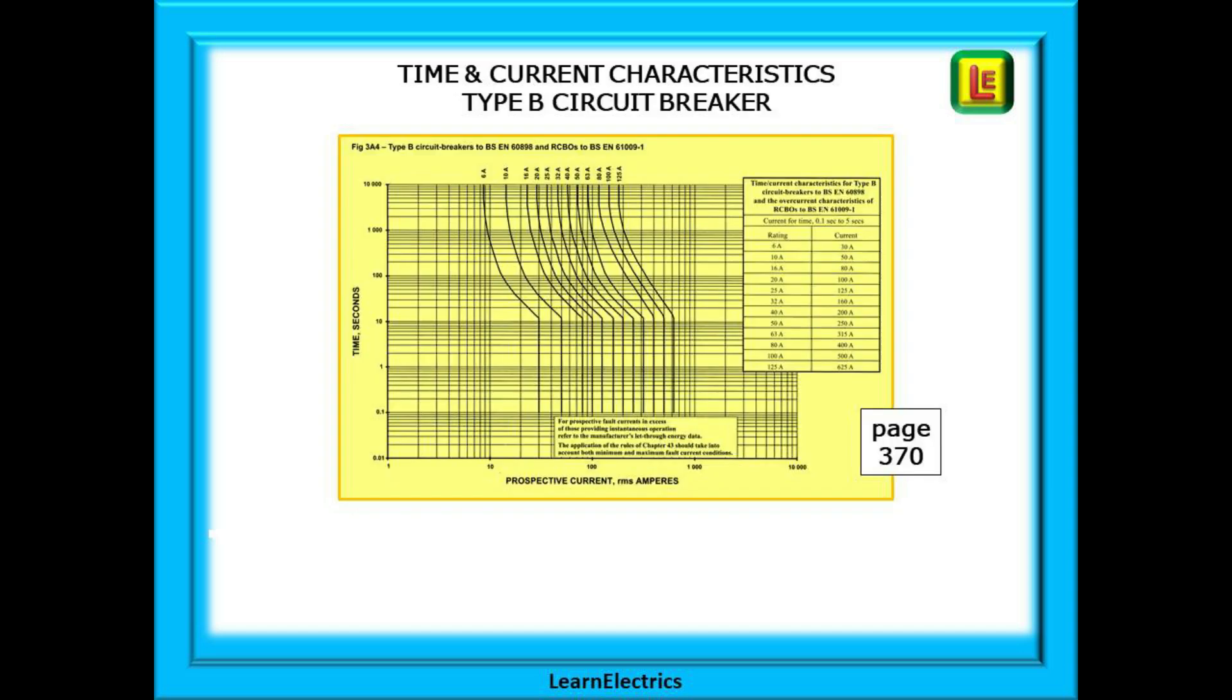Shown here is the chart from page 370. This is the time and current characteristics for a type B breaker or RCBO. If we know the time we want the breaker to operate in, this chart will tell us the fault current that must flow. In other words, time and current characteristics.